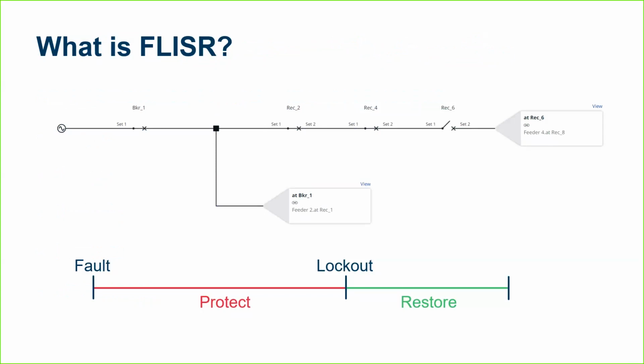So let's get to FLISR specifically. What is it? FLISR stands for Fault Location, Isolation, and Service Restoration, as Tristan mentioned in his introduction. What is that? Well, when a fault occurs on a distribution system, the first thing that should happen is a protective device should detect it and react to it. So fault occurs, protective relay should trip. That has nothing to do with FLISR. So in the bar along the bottom, that whole red protect region, that's the protective relay. FLISR does nothing here. Most faults are temporary. They resolve either by the passage of time, brief amount of time, or by reclosing.